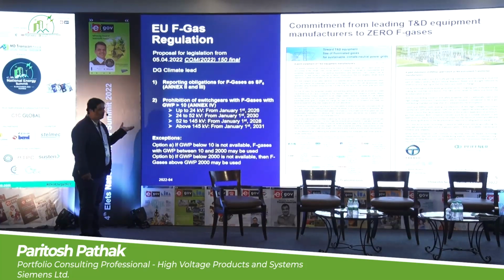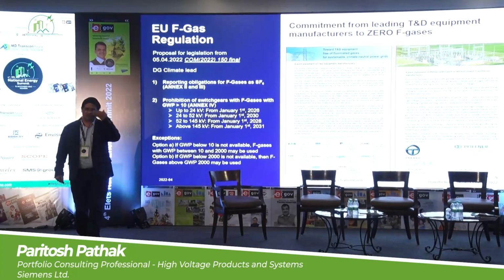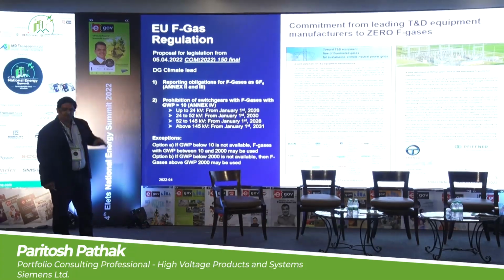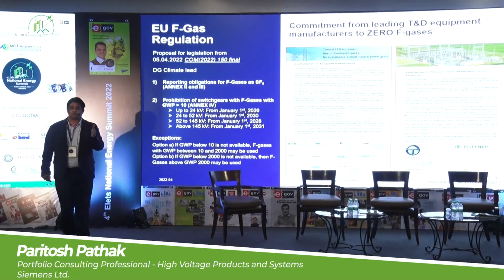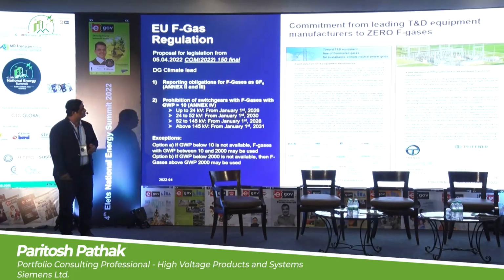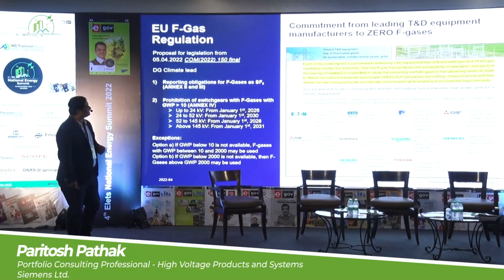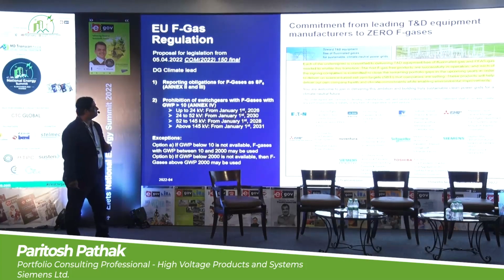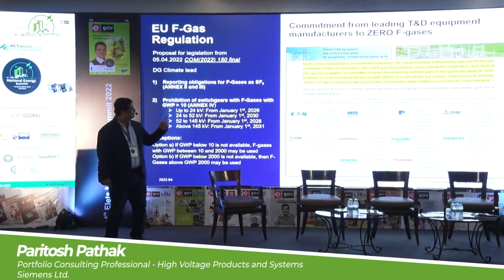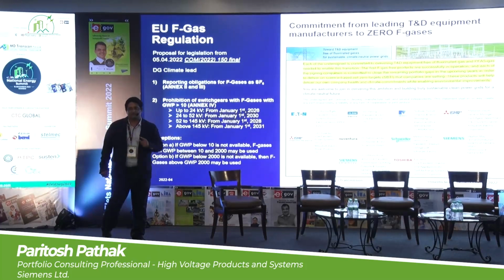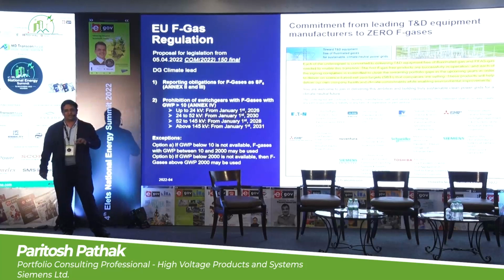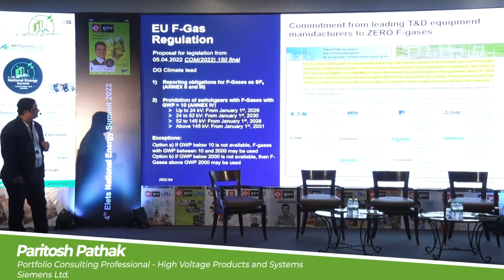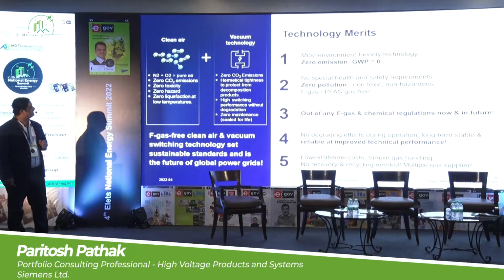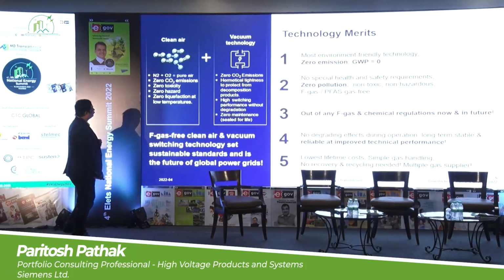This storyline, from the Paris Agreement till here, is putting pressure on T&D equipment manufacturers to look for another source of insulating media. And here comes the commitment from the people: each undersigned is committed to delivering T&D equipment free of fluorinated gases and PFAS gas needed to enable this transition, based on science-based net zero targets, with a lot of energy invested in R&D. Now, as Siemens, what we have done is develop a technology which is a combination of clean air plus vacuum technology.